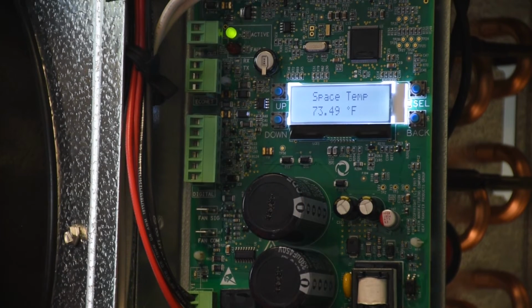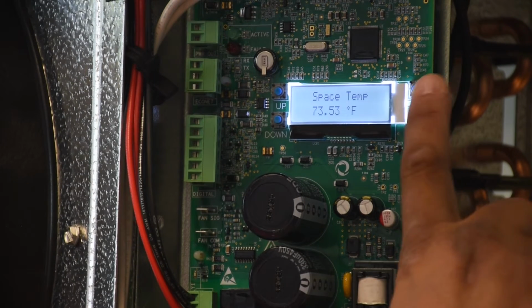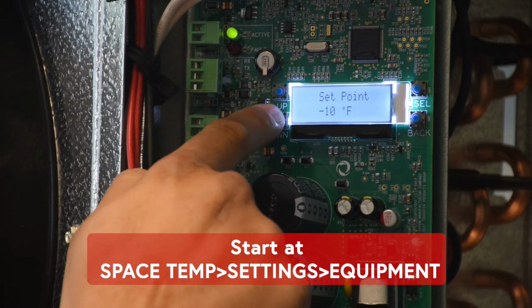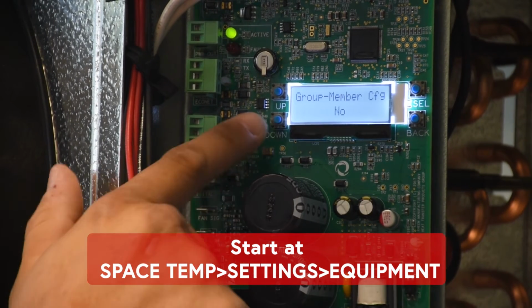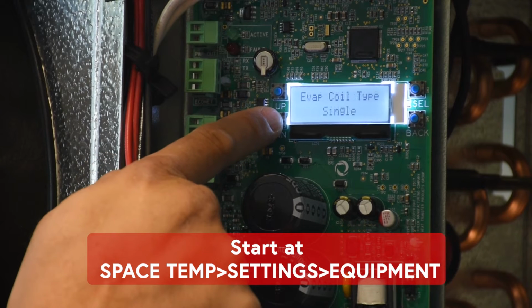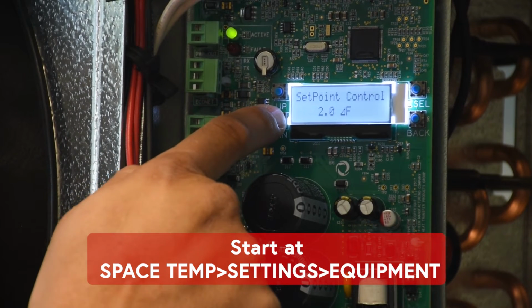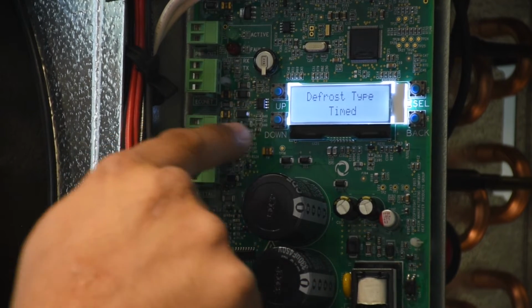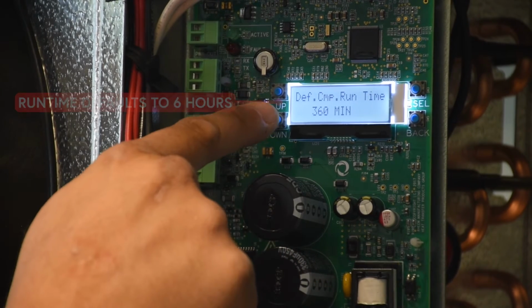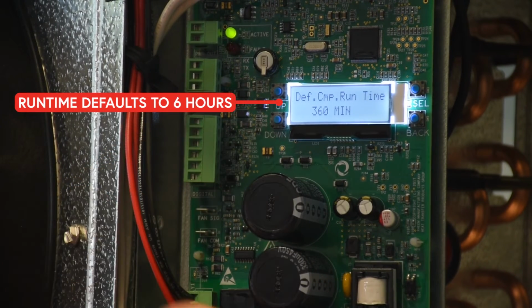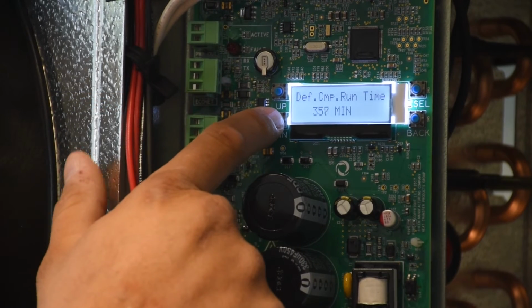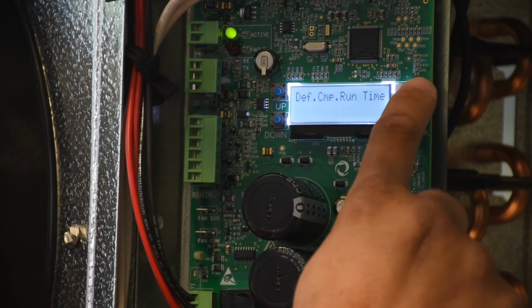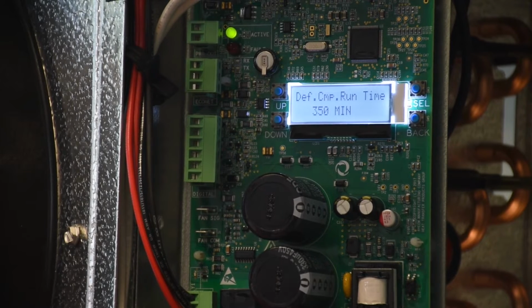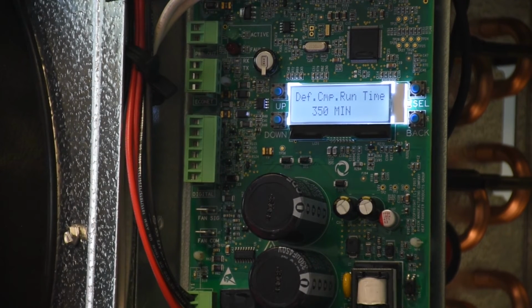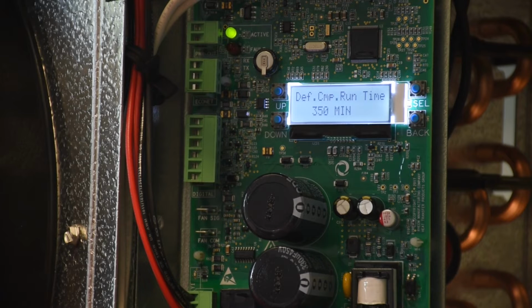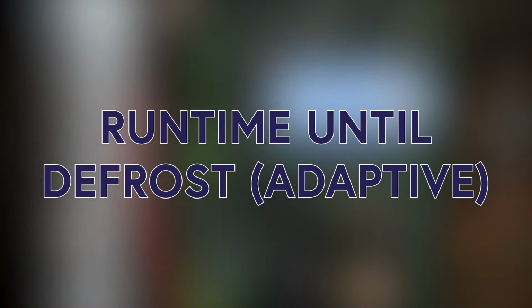To change the runtime between defrosts for a time defrost, you go to your settings, and then navigate down to equipment, and then scroll down. You're going to see defrost type for time defrost. The runtime you adjust will be defrost compressor runtime. It defaults to 6 hours, and you can adjust it up or down. And again, to confirm the change, hit select, and that's it. So this setting only applies on either a freezer or cooler if you are configured for time defrost only.